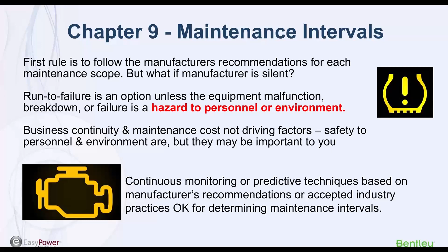At the end of the day, remember that business continuity and maintenance costs are not necessarily the driving factors - the driving factor is safety, though costs will of course be important to you. Alternatives come in when you can install continuous monitoring or use predictive maintenance techniques based on manufacturer's recommendations and accepted industry practices - those are okay. You can change maintenance intervals if you have a rational basis and good information. But again, the key issue is whether you're controlling the risk to personnel and facility operations from equipment failing to operate as expected. You need to assess things like physical condition, criticality, and operating environment.